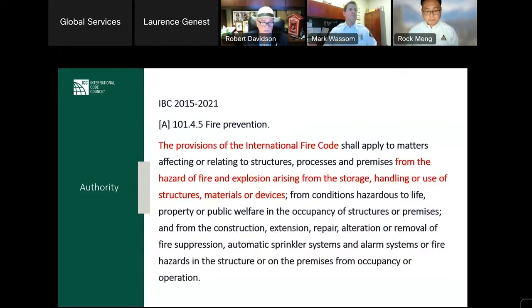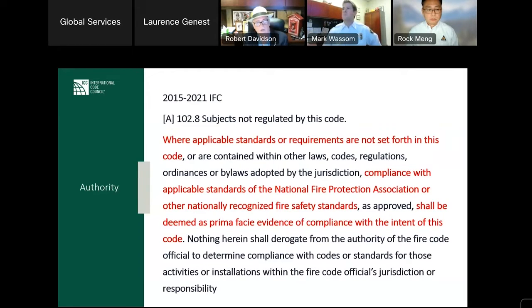Next slide, please. So besides the building code, the fire code's goals are the same when it comes to fire and explosion. Next slide, please. So one of the key things is that there are tools in the administrative portions of many different codes, whether it's NFPA, the ICC codes, or other governing bodies' codes. If the requirements aren't in the code to address the hazard you've recognized, there's language that generally gives a code official the ability to go to other nationally recognized fire safety standards to show evidence of what to comply with. It's a tool for you to be able to reach out and address requirements. Next slide, please.